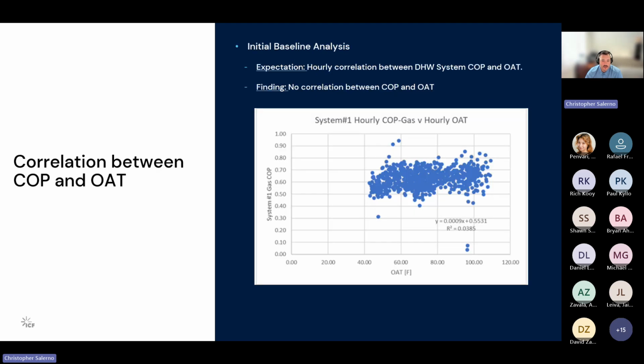And so here we basically tried to characterize or find a relationship between COP and OAT. So COP is the coefficient of performance of the gas absorption heat pump, and OAT is the outside air temperature. So this is measured weather station data, typically from CalMac, that we pull in to be able to see if this COP, the performance and efficiency of the system, is tracking with the outside air temperature, that is, whether the outside air temperature is affecting the performance of the boilers to be able to meet the same demand, assuming that the hot water demand is independent of the system that is providing that.